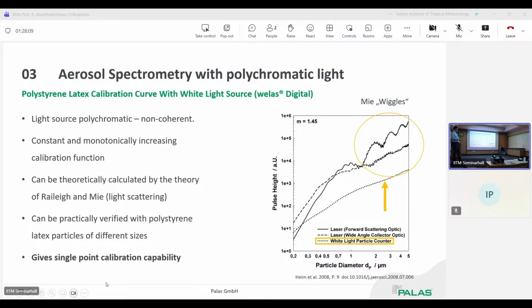And so we used white light, in this case xenon sources, and the calibration curve of the white light source is very clear, constant, monotonically increasing. And this is our calibration function, which we use for the different devices. And we verify this calibration function also with latex particles. So we can clearly distinguish the different sizes of latex particles, because this is the latex curve, the curve that our devices, if calibrated correctly, fit experimentally. And if they experimentally fit, then we can use this for measurement.